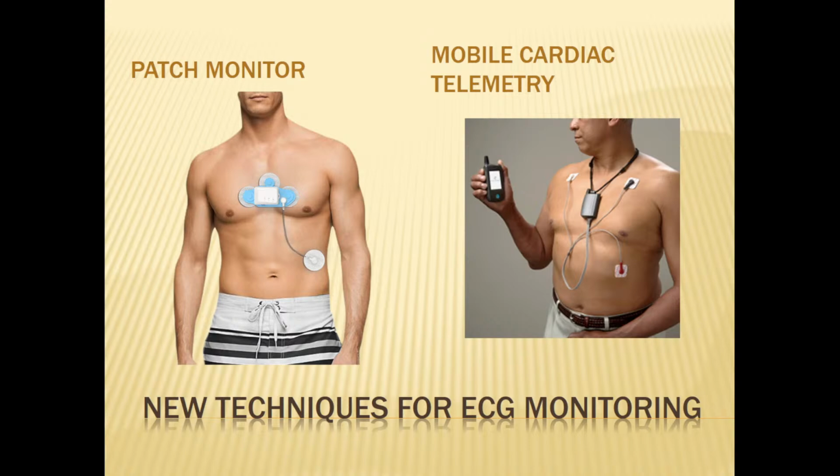They don't disturb the patient too much and compliance of the patient is good. But if electrodes are very close to each other, the amplitude of the P wave, QRS complex and T wave is very small and very difficult for the doctor to see small pathology, especially P wave pathology. So this monitor also has some limitations.